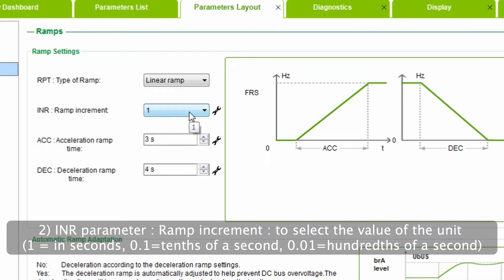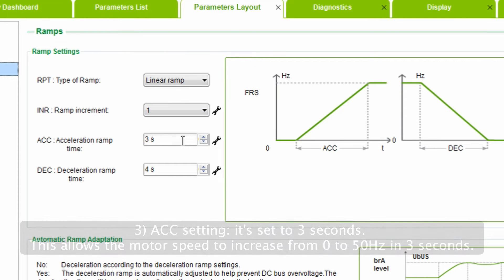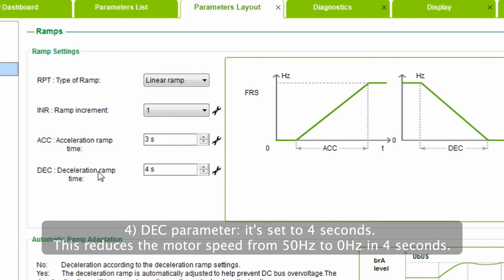Number 2: INR parameter, ramp increment, to select the value of the unit. Number 3: ACC setting. It's set to three seconds. This allows the motor speed to increase from zero to 50 hertz in three seconds.